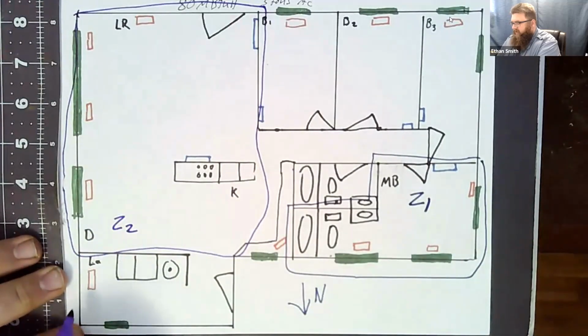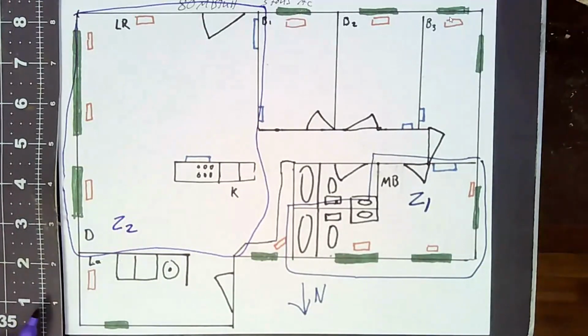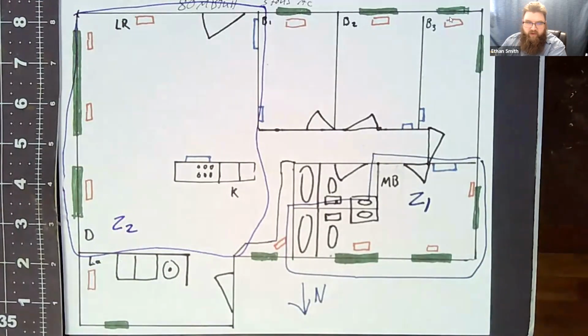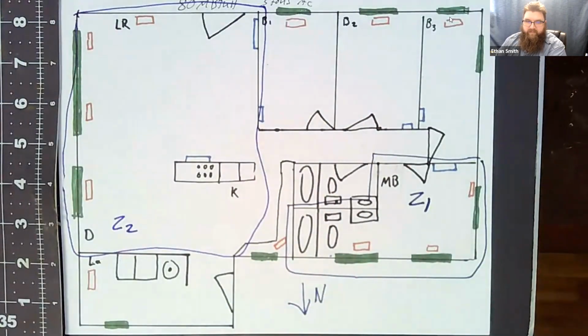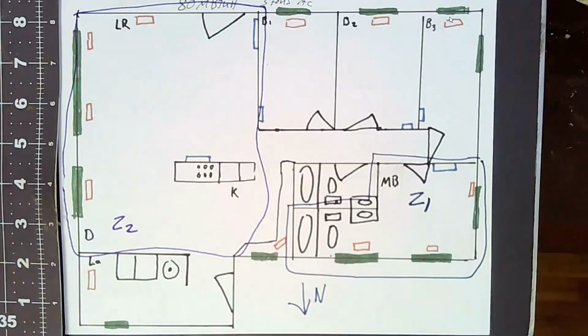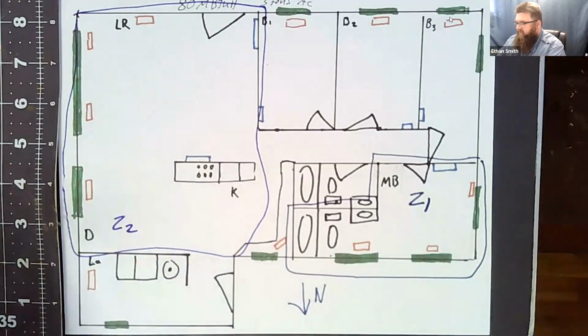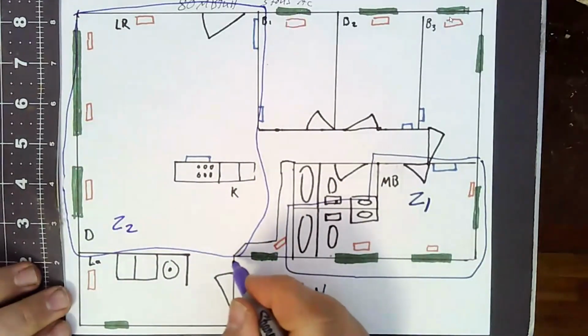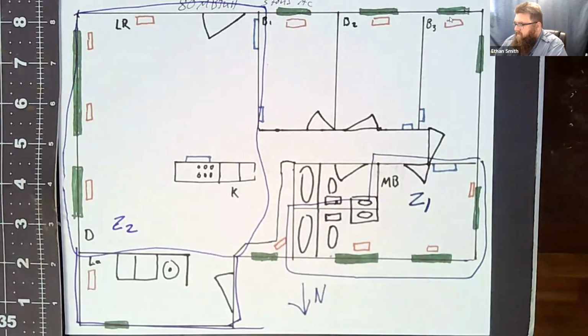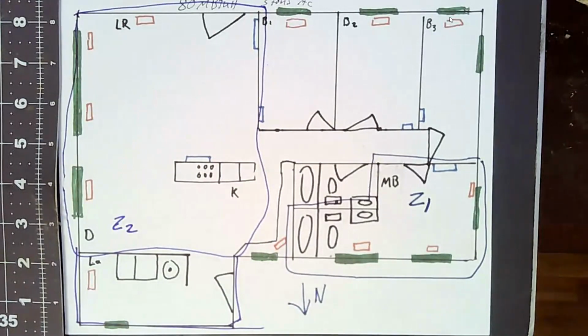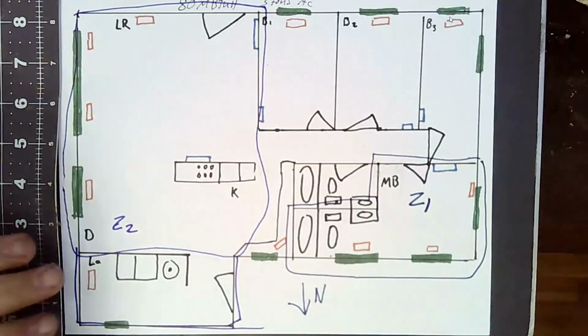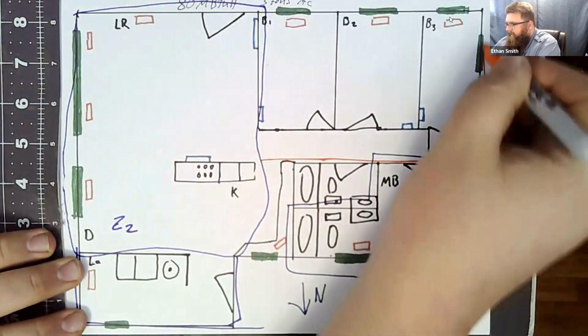Okay. So if we wanted to have this as its own zone, this only has one run, which is only going to give me 120 CFM on a 3-ton unit. Is that going to work out for us? Probably not. You'll also notice there's no door between the laundry room and the kitchen. Well, then you better include it. Okay, so let's tie it in with zone 2. Okay, so that leaves us 3 bedrooms, with 1 duct each, so you should probably make it 1 zone for all 3. Okay. Agreed. Okay, so we've broken this up into 3 zones.